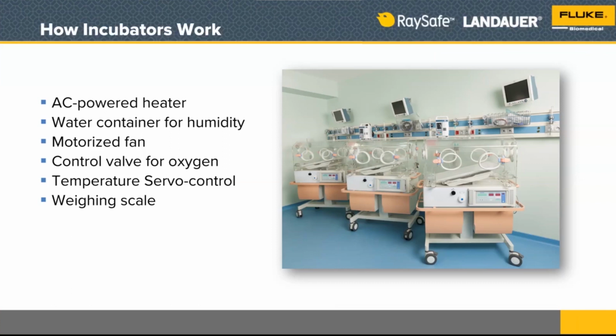The servo control has a couple of different ways that it controls. If we use the skin temperature of the baby or a rectal temperature of the baby, that can be the control of the incubator heater, so that the incubator is going to turn on the heater and warm it up, or turn it off and cool it down, depending on the actual temperature of the baby. If we use the rectal temperature probe, that gives us more of a core body temperature of the infant. If we use the skin temperature, it's just the skin surface temperature. It doesn't really give us quite the detailed measurement of temperature that the baby's vital organs are at. So a lot of times the rectal probe is the better one, depending on how sick the baby is.